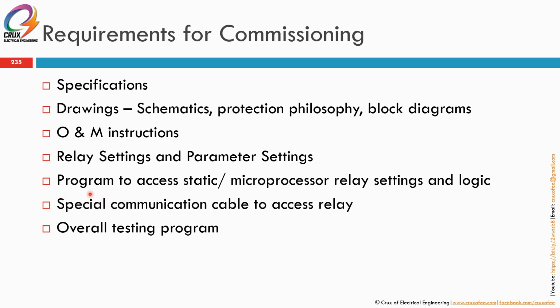So if you're using, for example, the Siemens relay, then you will require the Digsi program. Or if you are using Schneider, you can just download it from the Schneider website, or for GE, you can just download it from the GE Multilin website. They are free. Then you need a special communication cable to access the relay. Some modern relays, we can just use the normal RJ45 TCP/IP cable. But some relays may require a Modbus RS232 or RS485 connection. For RS232, you have to check whether it's a normal straight cable, meaning point to point, or whether there is any twisted pair in that cable connection.